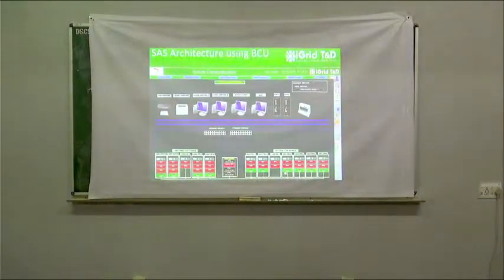So all the information which is there in these relays is collected within this gateway, and through this gateway we send the data, for example, to an SLDC, that is State Load Dispatch Center, or to a control center, using different protocols. We usually send the data using IEC 101 or IEC 104 protocols. That data can be sent through different ways of communication. When we are sending a serial communication, we send the data using PLCC, that is Power Line Carrier Communication.